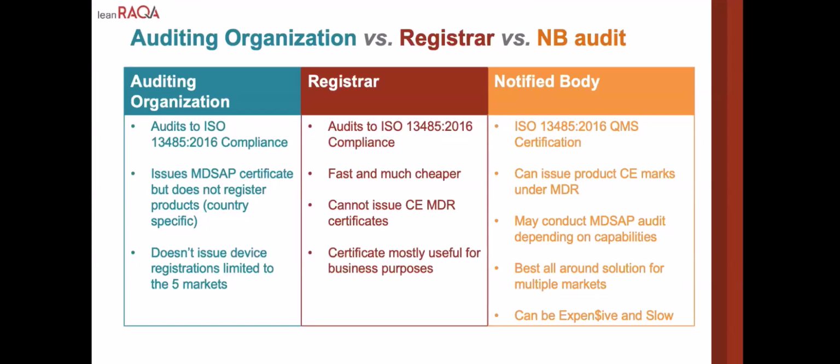Whereas a notified body, they also can issue an ISO 13485 cert. They can issue CE marks under MDR. They can issue quality management system certificates under MDR. They may or may not be able to conduct an MDSAP audit, depending if they're also designated as an audit organization.